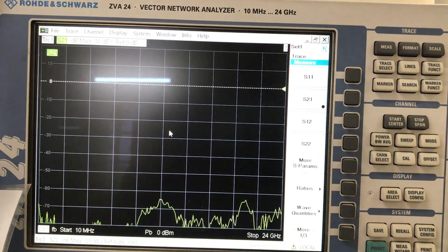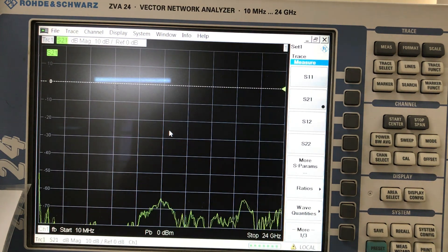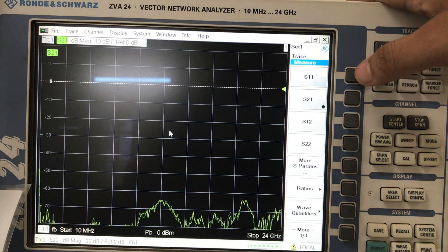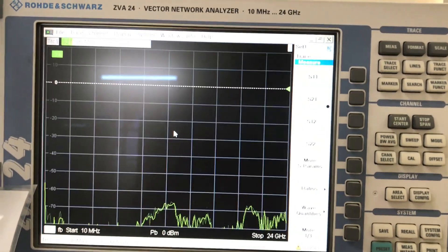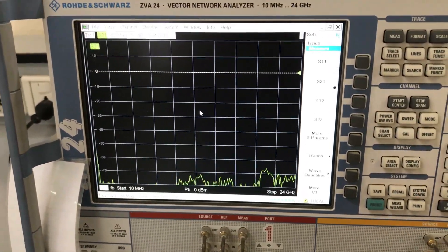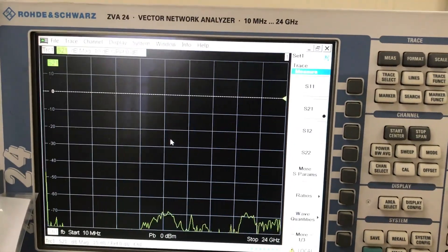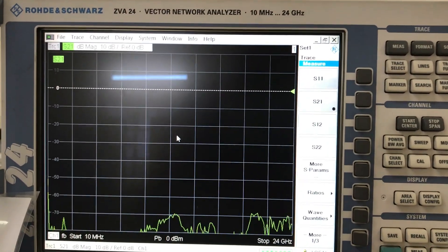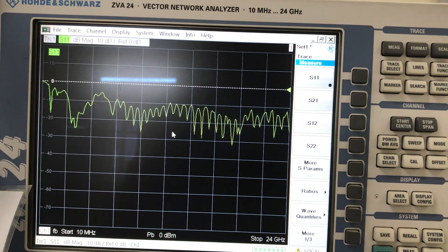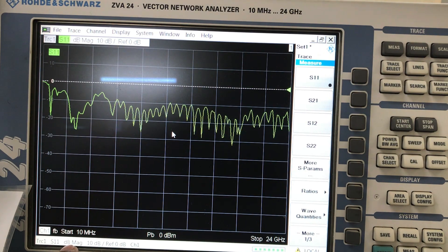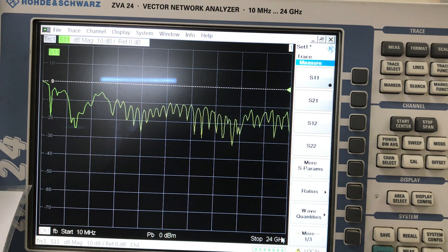I already have a calibration done, so I'm just going to plug in. Since my antenna is connected to port one, all I need to do is click on S11. Here is the S11 resonance frequency displayed from 10 MHz all the way up to 24 GHz.